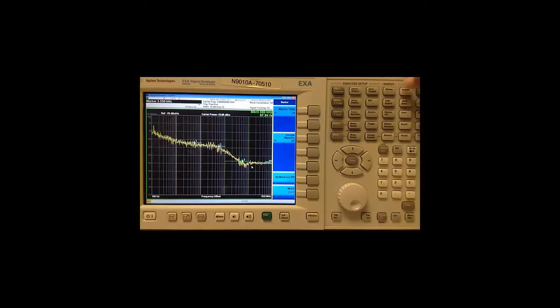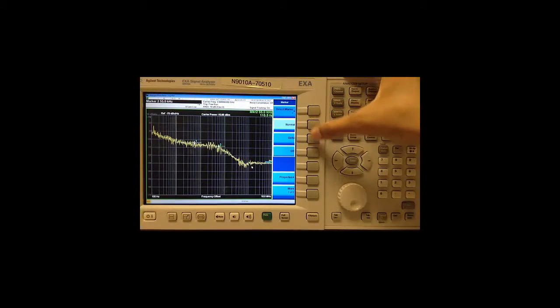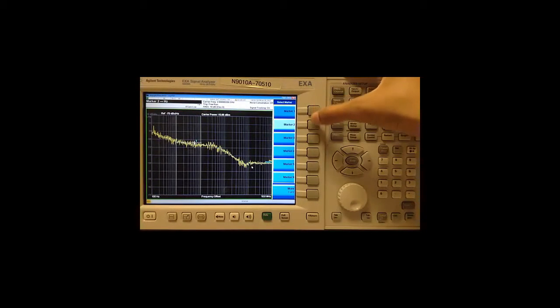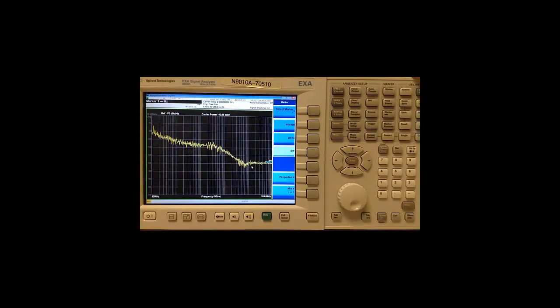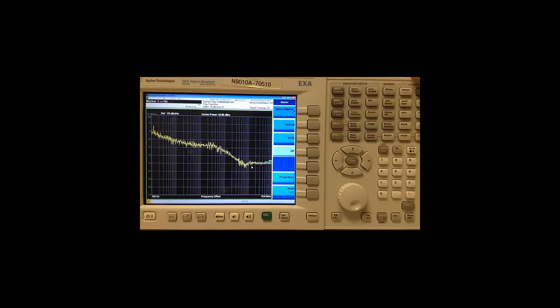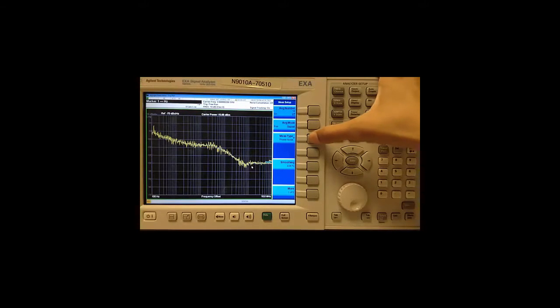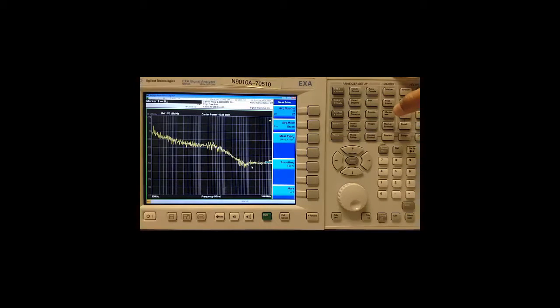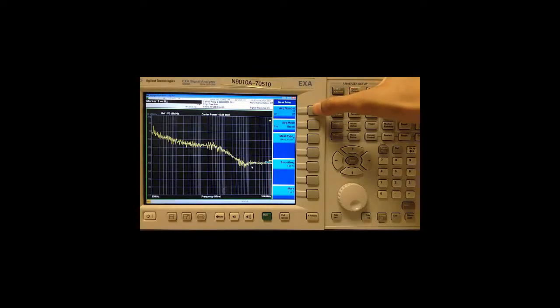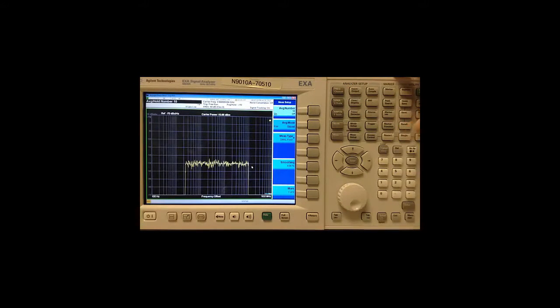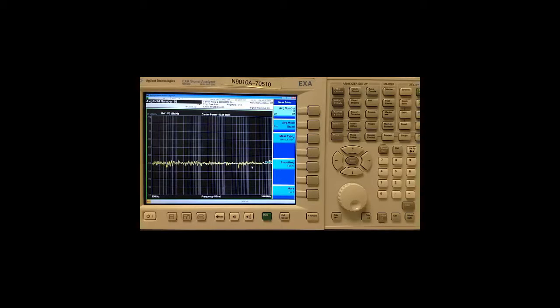So let's turn all of this off and perform a noise floor cancellation. To do this, first I go to measure setup, change the measure type to noise floor. Then I set my average number. I set it to average and press restart which will average the noise floor about 10 times. You can see it updating over here.